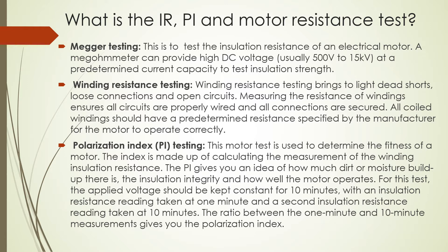Winding resistance testing brings to light dead shorts, loose connections, and open circuits. Measuring the resistance of the winding ensures all circuits are properly wired and all connections are secured. All coil windings should have a predetermined resistance specified by the manufacturer for the motor to operate correctly.